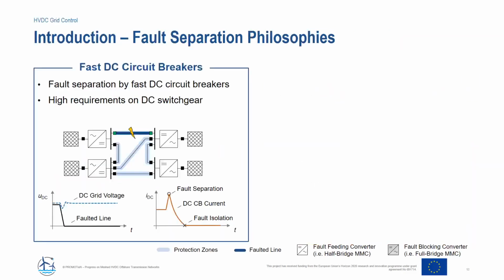So as already introduced regarding the protection demonstration of today, we will focus on the full bridge-based demonstration strategy. However, I quickly want to motivate why we look at this strategy and what is the background. So first of all, once it comes to HVDC grid protection, for sure it would be desirable to just install fast DC circuit breakers at each line end and treat every line as individual protection zone, so similar to AC grid protection system. In case of a fault, the DC voltage collapses and the current quickly rises.